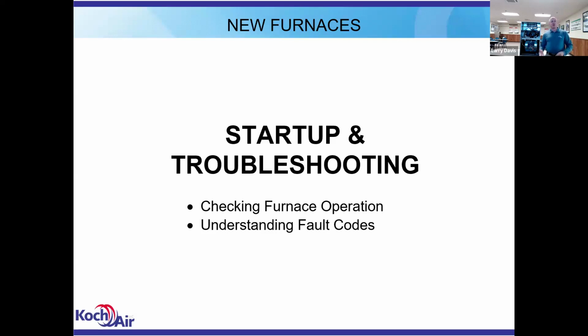When these furnaces first came out and started being installed in the field, a lot of the phone calls we were getting were about how to set the fan speed. Just a reminder, when you're checking the static pressure on the chart for the furnace, the return is taken in the blower section or after the filter, between the filter and the furnace. The supply is taken between the furnace and the coil. That supply static pressure is not taken after the coil. That chart only applies to what's inside the furnace cabinet.